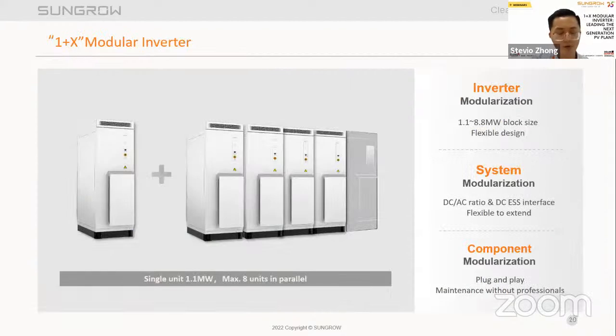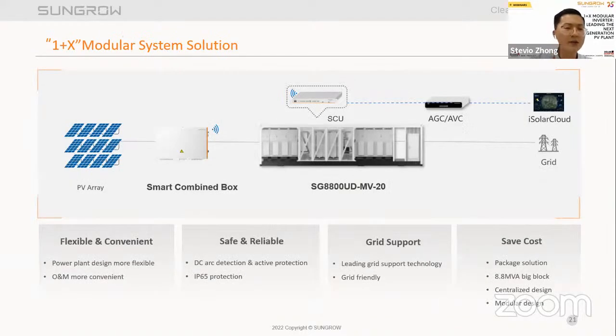To tackle the problems above, our company promoted 1+X Modular Inverter in 2021. It combines the advantages of string inverters and central inverters. The power of single unit is 1.1 megawatts, and the maximum number of units for this product is 8. The main characteristics of this inverter is modularization, such as inverter system and component modularization. Along with this project, Sungrow could provide package solution.